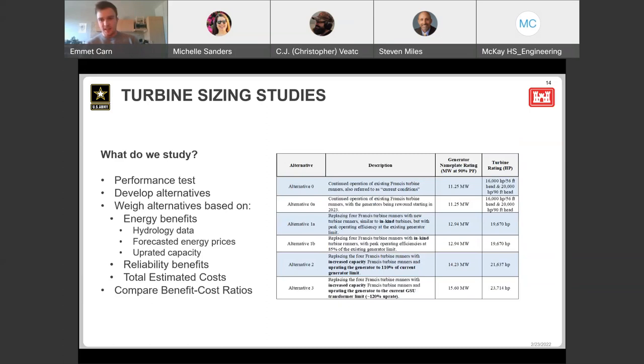So what do we study in these planning stages of sizing studies? First we do a performance test - we go out on site, install sensors on units, and determine how efficiently the unit is operating now. Once we have that baseline, we can develop potential alternatives. One alternative might be to let the unit run as is and keep the current turbine in place. Other alternatives might be to replace the turbine but keep it the same size, or to uprate the unit and create a bigger turbine that can produce more power with more flow.